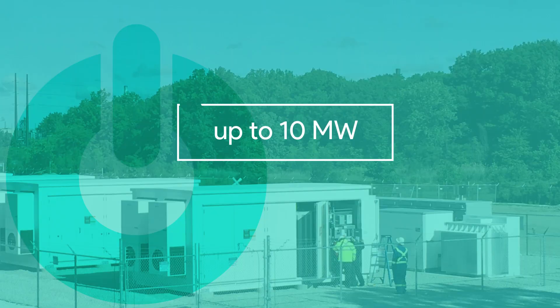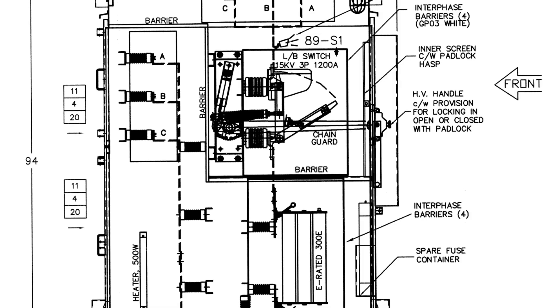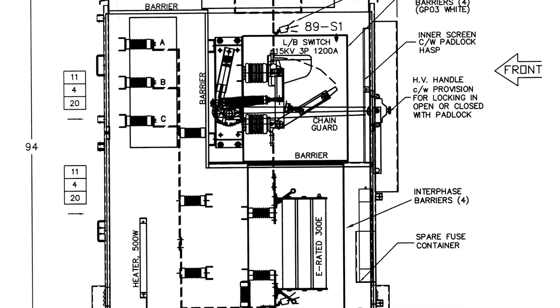It has the ability to inject and store up to 10 megawatts of electrical power, interconnected directly at the customer's primary medium-voltage distribution system. The plant is comprised of six 1.67 megawatt energy storage blocks, each including transformer, inverters and battery enclosures with associated HVAC and control equipment.